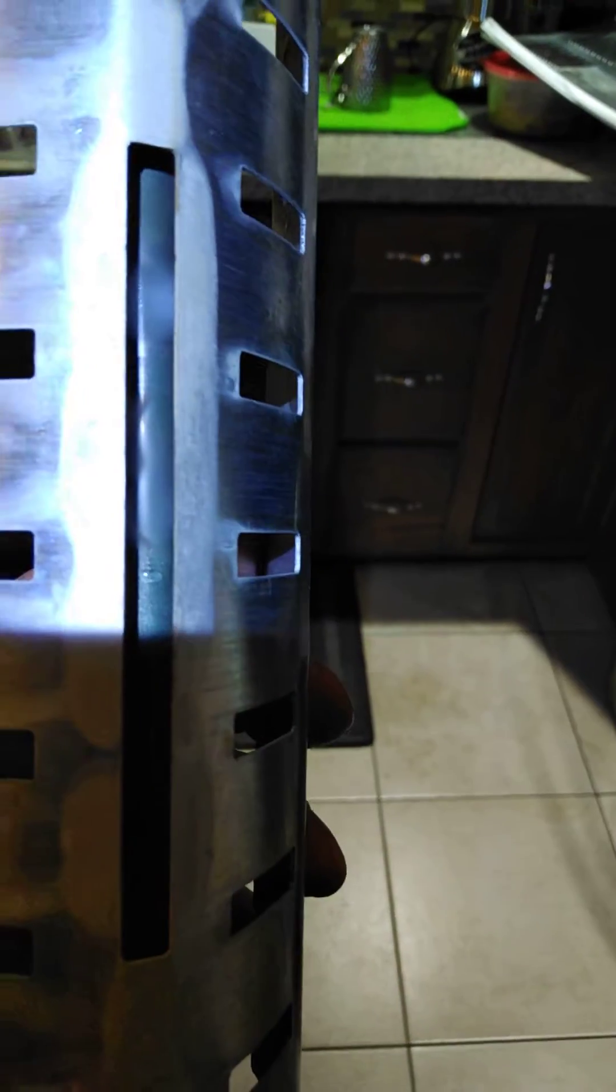Turned out to be a bad defrost heater. This is the old one here. You can see how black the element is.